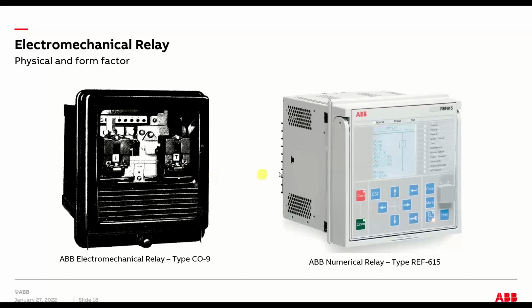So this is just a follow-through on the original concept, because it worked. This was a good design. It worked well, and it was copied over and brought forward into the new technology. But this relay here can do overcurrent 51/50 on a single phase. That's it. So on a normal three-phase breaker, you'd have one of these for each phase, A, B, and C. This guy does all three phases, plus almost any other thing you can ask it to do. So a panel that might have had 4 or sometimes even 6 or 9 of these devices on it for one breaker has now been reduced to a single box.